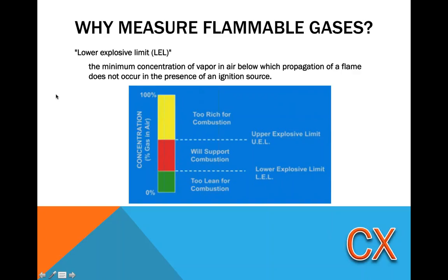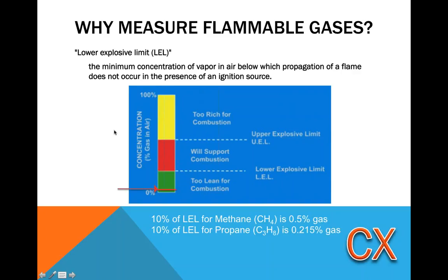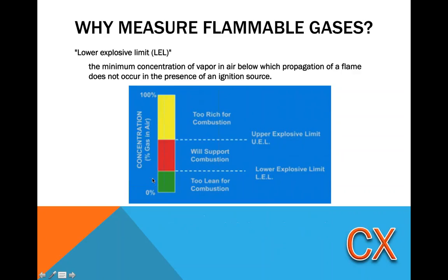So the lower explosive limit is illustrated here. And in this situation, you can see where the lower explosive limit is reached for a concentration of gas in normal air. That means air which is 20.9% oxygen approximately. In this situation, it's green. That means you're below the lower explosive limit, which is too lean for combustion, not enough gas available for combustion. And then it moves through the red range, where the concentration will support combustion, the concentration of gas in normal air. And then it can move into another range where there's a higher concentration of gas, where it's too rich to support combustion. There's not enough air for the fuel available. That's called the upper explosive limit.